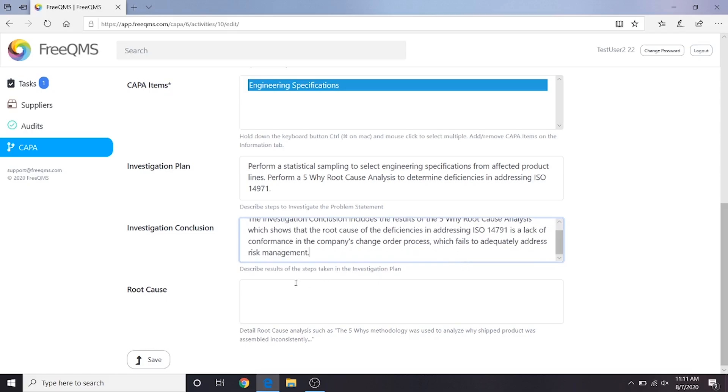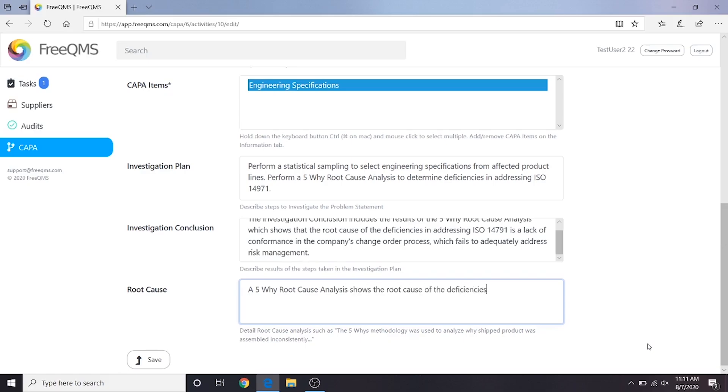For our root cause, we'll put: A 5 Why Root Cause Analysis shows the root cause of the deficiencies in addressing ISO 14971 is a lack of conformance in the company's change order process, which fails to adequately address risk management.